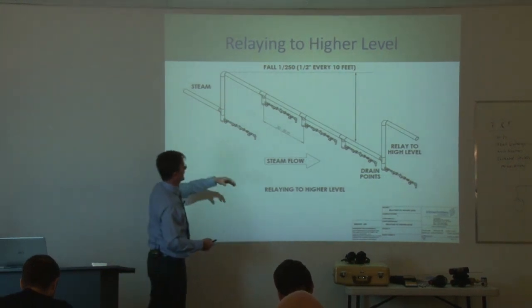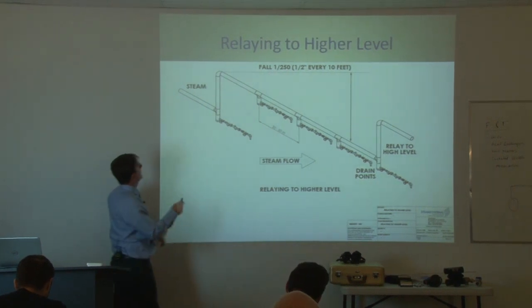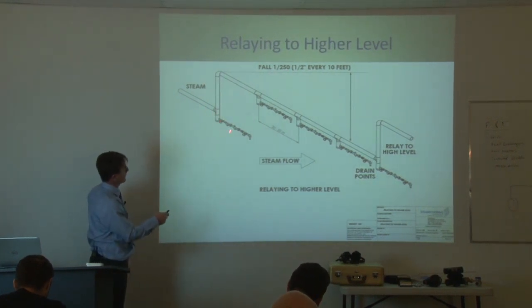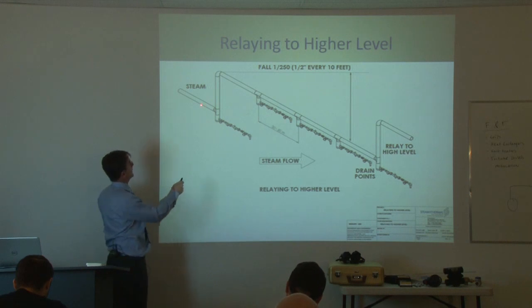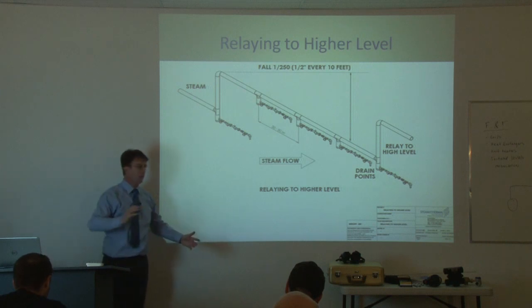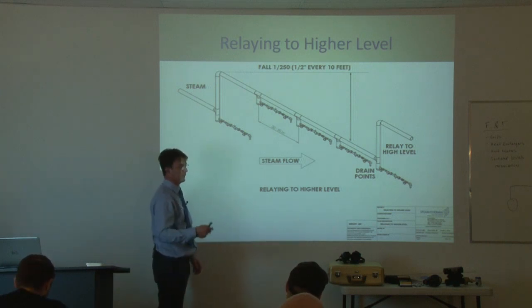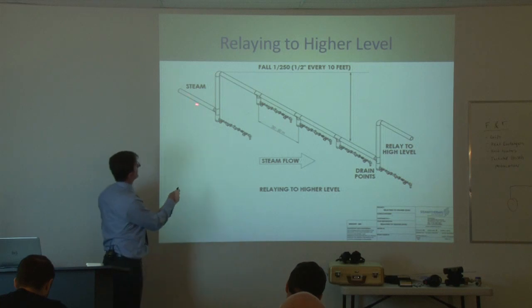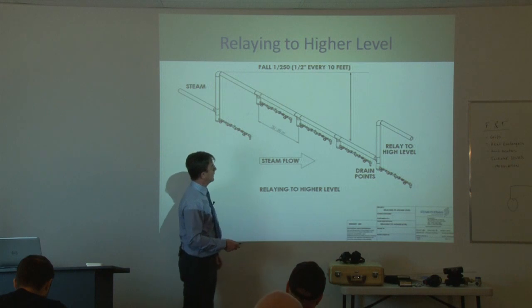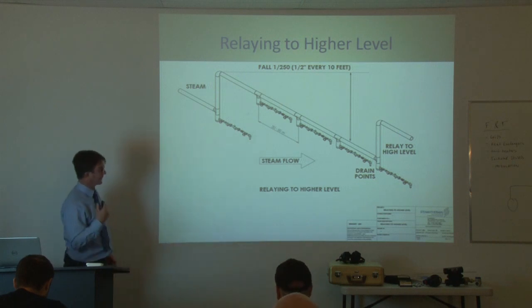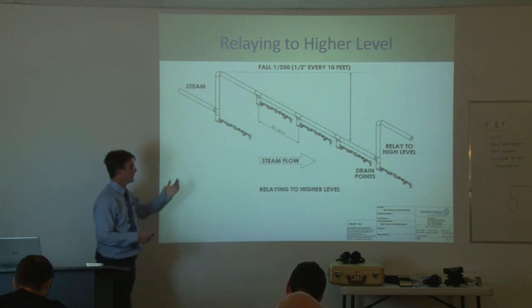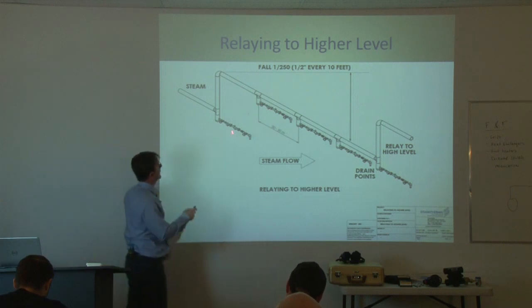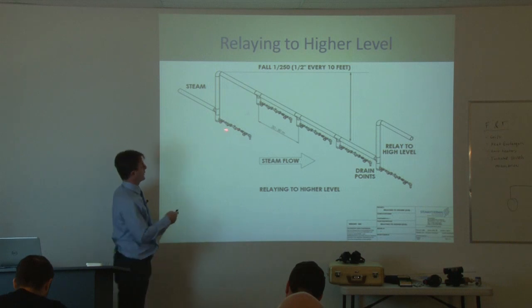And that's to prevent water hammer because the condensate, as I mentioned, is going to be traveling at a very high rate of speed. And the steam is pushing it along. So if we're not taking care of draining the condensate from our system, we'll end up with kind of a tsunami. Because that pressure is just pushing the water along, and it builds and builds into a slug, and it can actually take out the pipe. It can break the pipe apart. It can rip off flanges. It gets very, and it's annoying sound, but it's also very dangerous. So steam that is properly designed, properly maintained, will not have that problem with the water hammer.